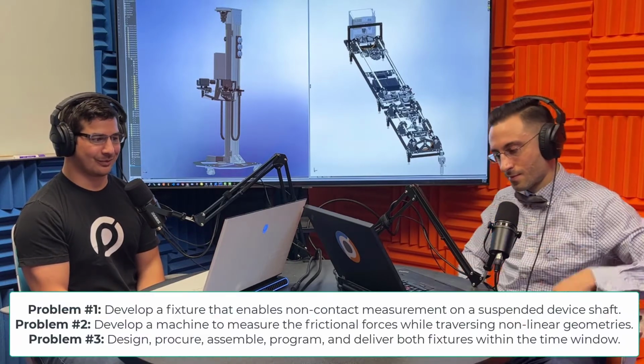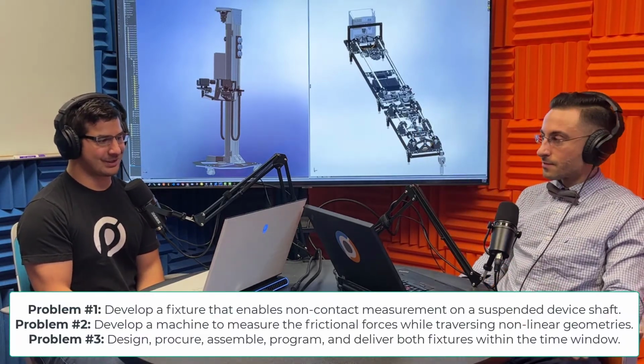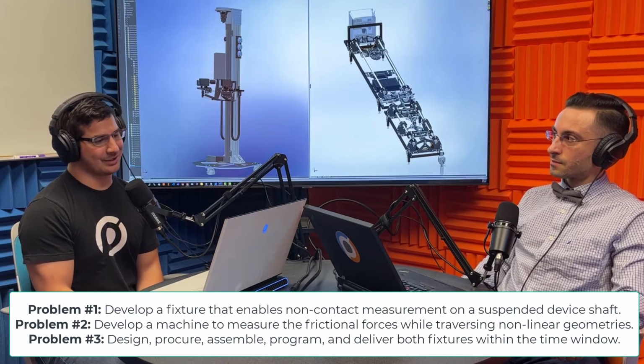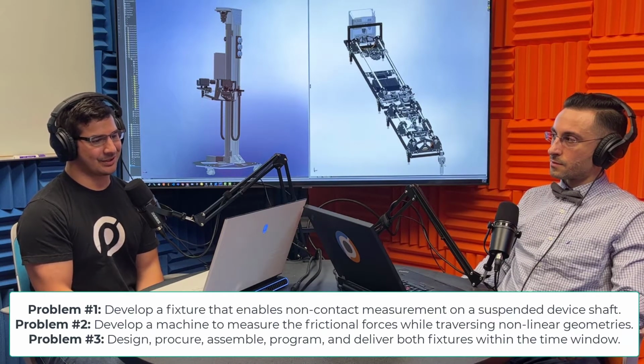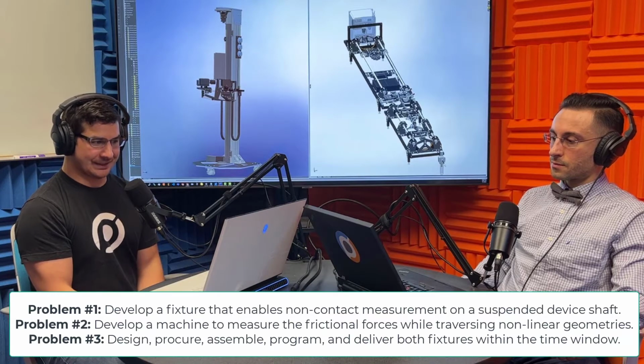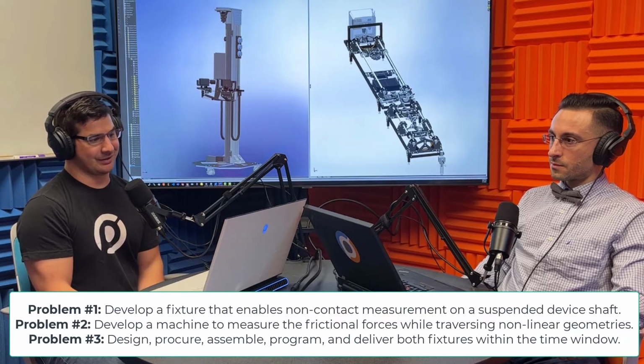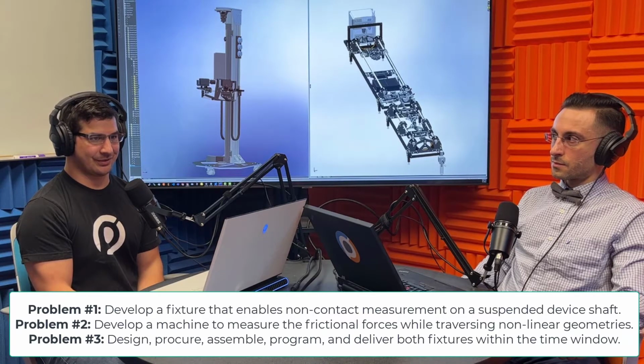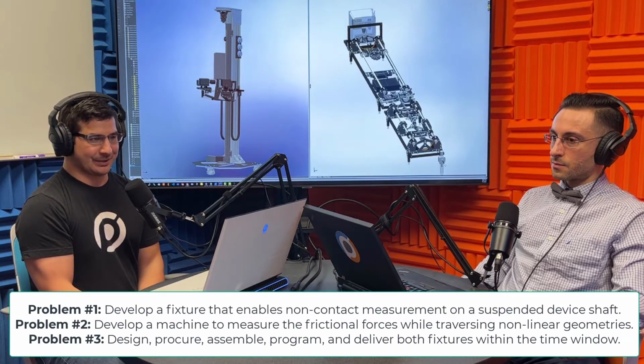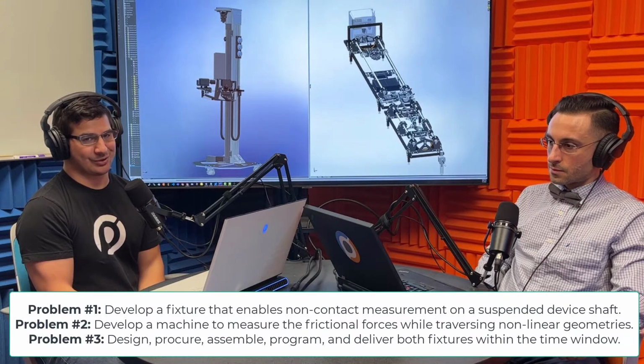Well, a 10-year-old, that would be a little bit tough. But the two problems here, are actually three, that I was trying to solve were: one, how to take repeatable and non-contact measurements on a semi-rigid medical device shaft. Two, a method to read or calculate the friction coefficients for nonlinear geometries. And three, design, build, program, and deliver those fixtures with a short lead time.